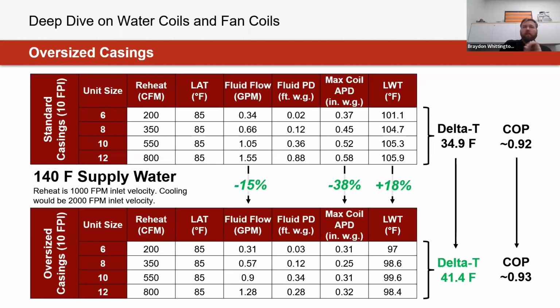So there are benefits for both: increasing our water side delta that's provided from our coil, decreasing our fluid flow, which affects how we're going to be sizing our pumps, and a reduction of air pressure drop. Where this ties in, though, when we look at a retrofit example, is: is it always possible to oversize a coil, or how much coil can we oversize before it becomes a concern? But we'll talk about that here in a little bit.